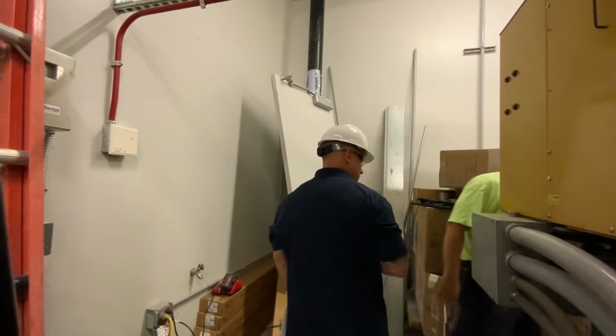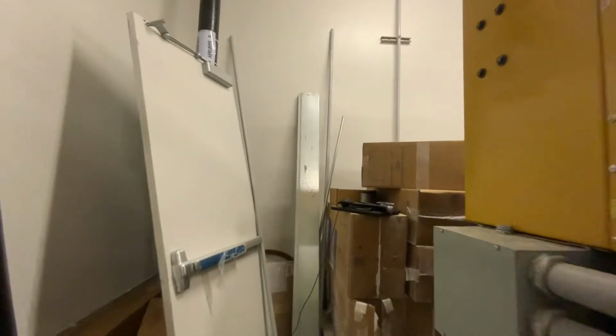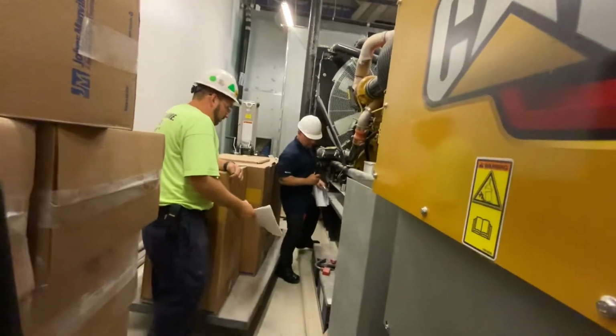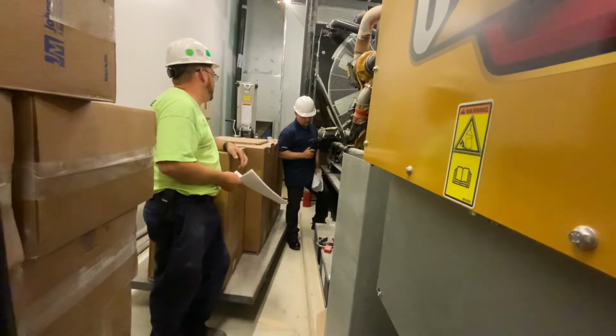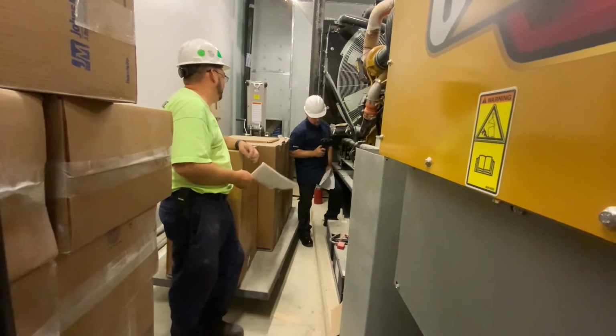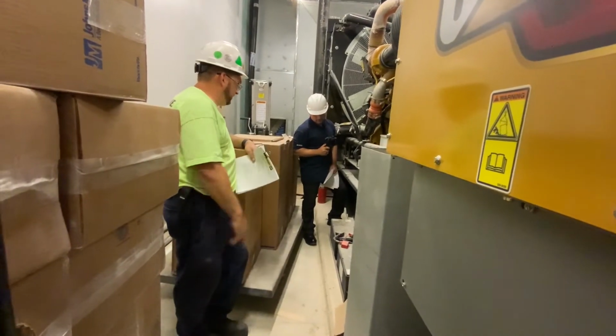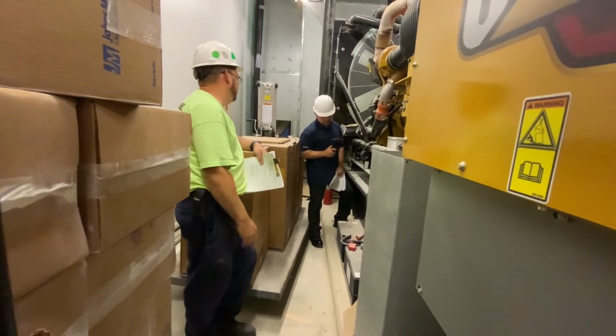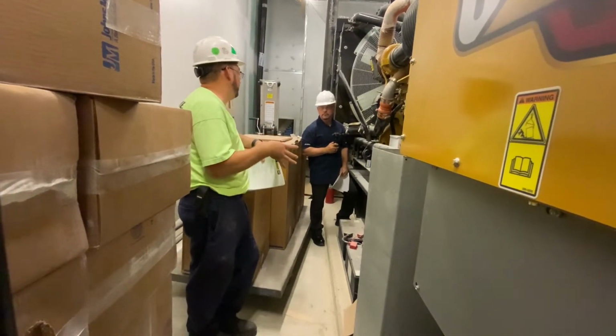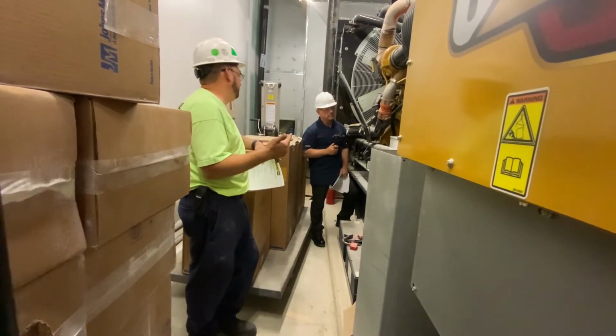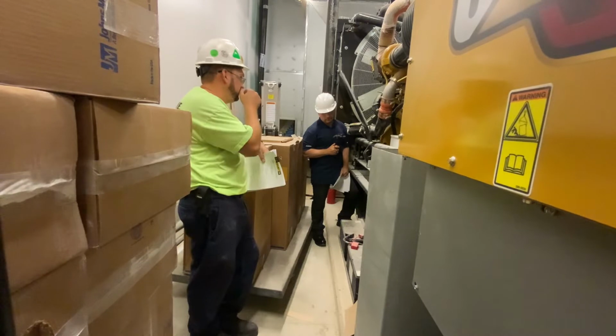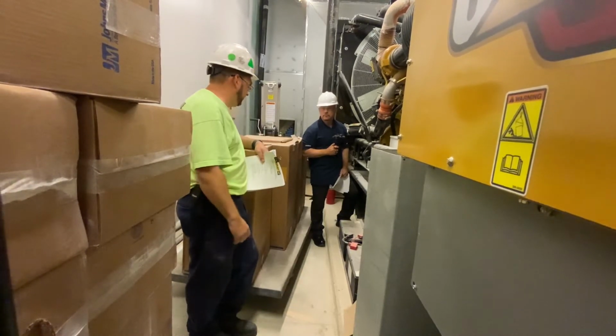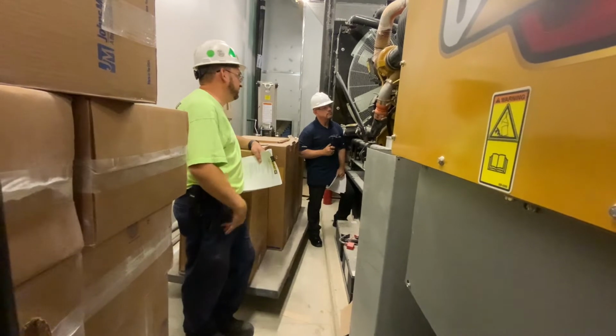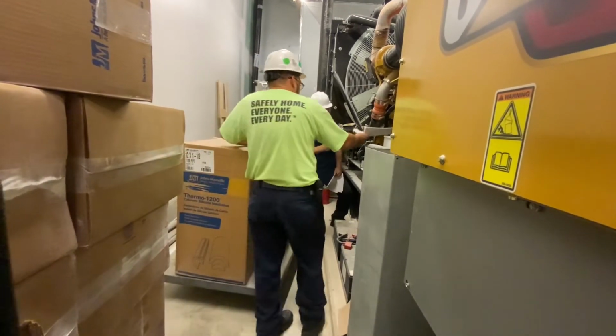Alright, batteries and other accessories. So, you have your batteries right here. These are what CAT calls a maintenance-free type battery, which basically means it's a maintenance-free style that can't have water added to it. It's just got a sealed cap on it as opposed to the vented caps from years ago. So it keeps a lot more water vapor in there. However, over time they still do lose water vapor because they're constantly being charged. And so basically CAT had to go to a design like that for a genset that's constantly being charged because it loses water vapor.